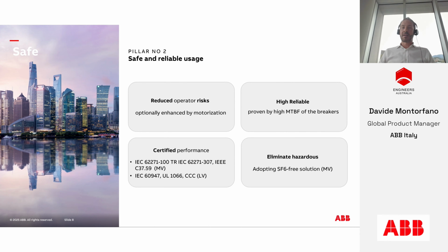So it means that the nominal current that we put, the short circuit withstand, the electric performance, and the interlocks are fully aligned with the standard requirement. This also makes a distinction, because our retrofit is not just done by very expert technicians, but everything that is in the label is fully proven. And this is unlike the typical solution that you can find in the market, called repair as a retrofitting. That means it's just a mechanical adaptation of a breaker to the system. So even if it's done in the perfect way, it's not possible to prove and guarantee the performance of the solution.